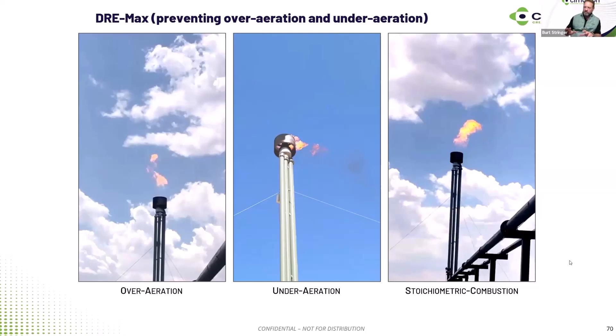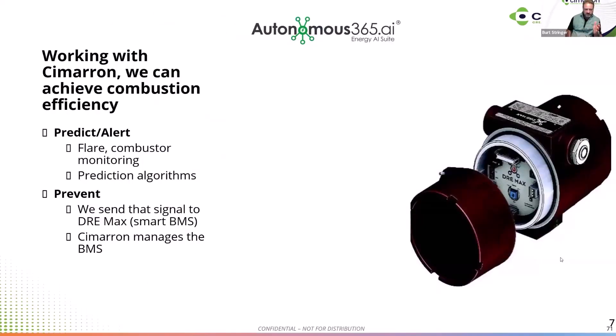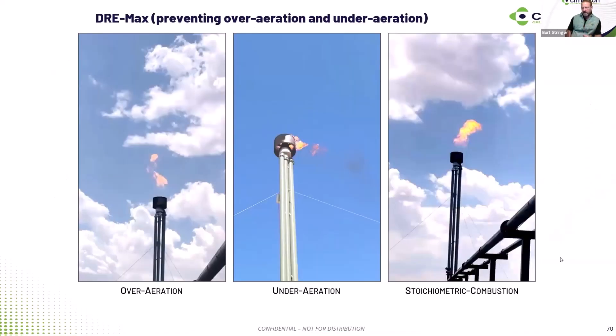Using our DRE-Max — which has been proven and tested in several basins and is part of the ARPA-DOE project — where we control that VFD and blower with site conditions automatically minute by minute to ensure proper airflow and combustion. You can see on the left where it's over-aerated and under-aerated, and then with DRE-Max on the far right — a clean-burning 99-plus DRE flare using technology and software.